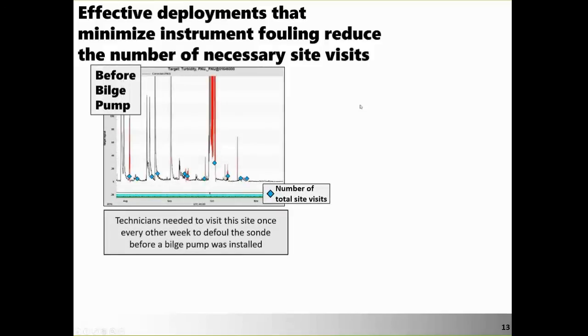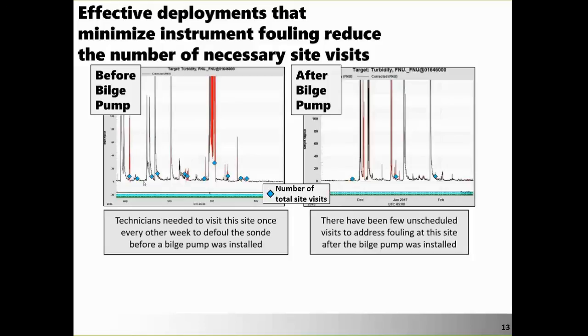Refining the deployment also reduces the number of site visits needed. Before a bilge pump was installed at one site, a three-month window shows blue diamonds representing times technicians physically had to go clean the instrument — about once every other week. After installing the bilge pump, we got a cleaner turbidity record and reduced the number of field visits, which is ultimately a cost savings that lets us reprioritize staff time.